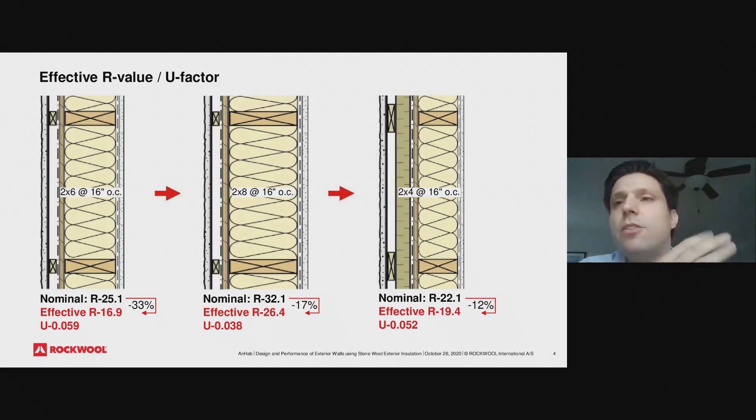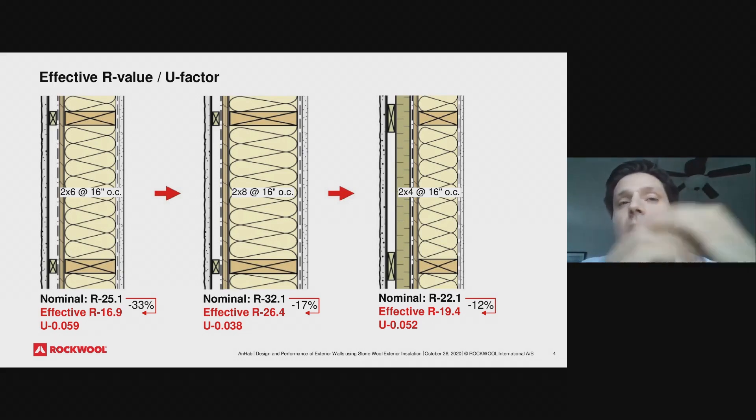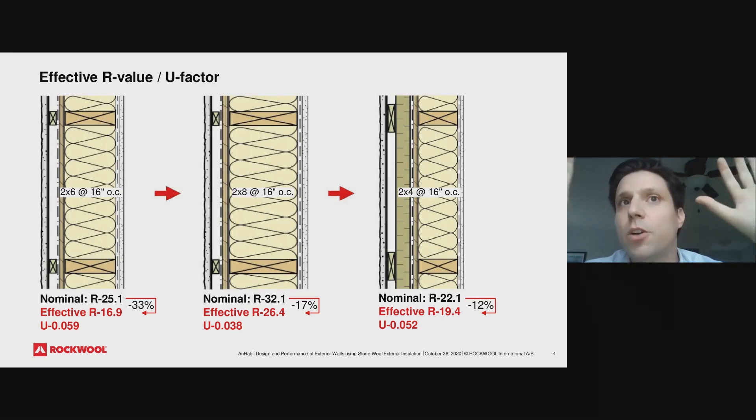A better solution — not just from a thermal standpoint but also from a durability and moisture standpoint — is to add exterior insulation. By adding one inch of exterior insulation and going to two-by-four studs with a three-and-a-half inch batt to fill the cavity, we end up with a nominal R-value less than the two-by-six wall, meaning we are putting less total insulation. But we end up with a much better effective thermal resistance because we have reduced thermal bridging — first by reducing stud size, but more importantly by adding what we call continuous insulation, or exterior insulation. This continuous layer actually reduces the heat flow going through our studs.